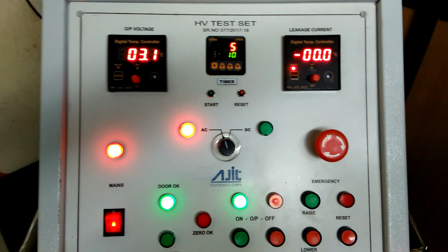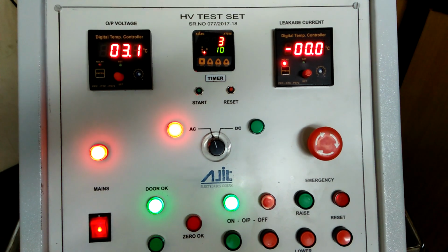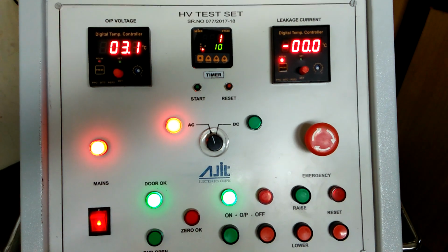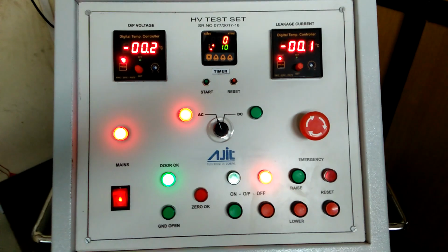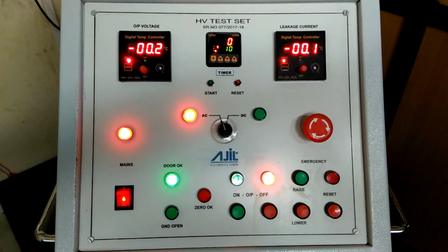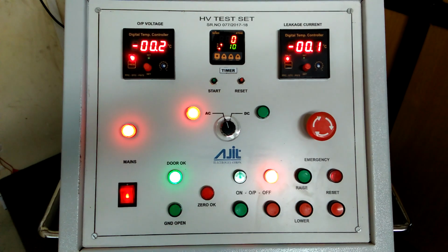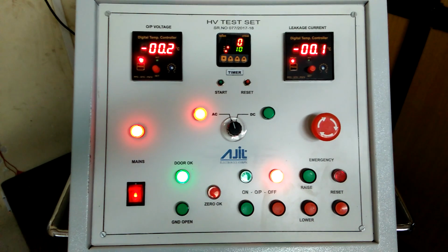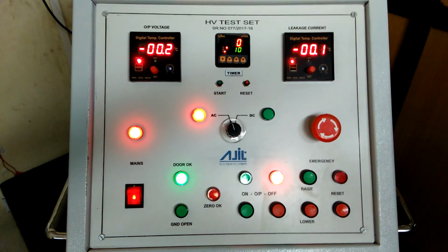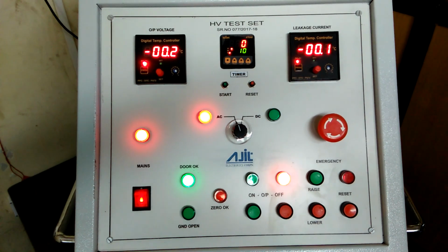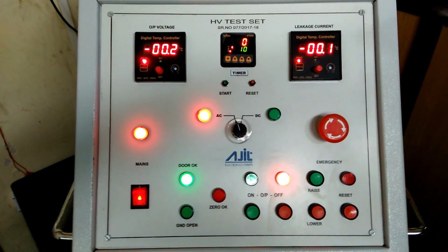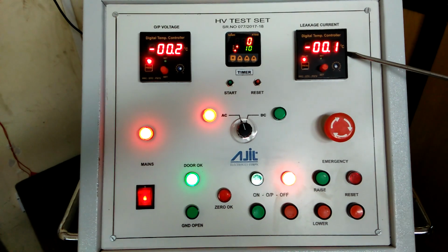It has got a pulse from the kV controller and the timer has started for the set value. Once the time is over, the timer trips off the output and the output from the terminal is put off. This means the test is completed successfully without overcurrent tripping.